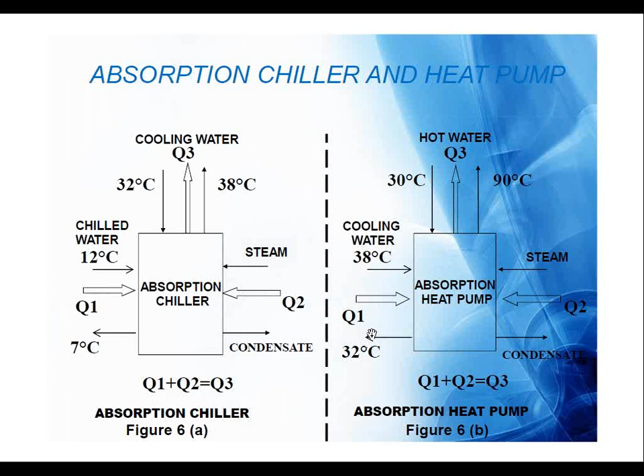So by the same principle, Q3 is equal to Q1 plus Q2. The same principle applies for the heat pump also. So Q3, which is an active heat, is equivalent to the energy conservation by considering the cooling water heat, which is getting dumped into the heat pump, and the active heat of the steam. This is how we are saving the energy, which is equivalent to the heat which is consumed in the cooling water circuit.